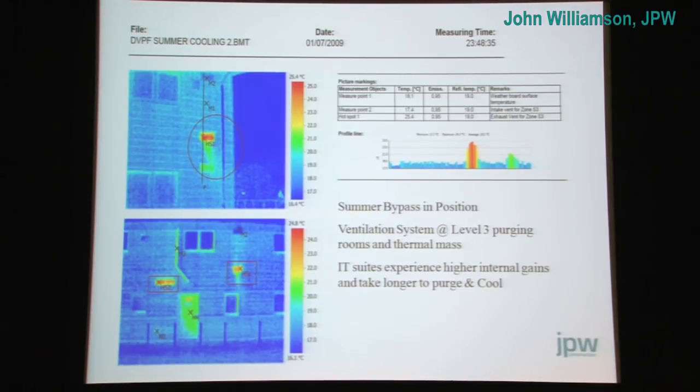We are heading for that double whammy. We've had the hottest summers and the coldest winters on record the last 2 years in a run. High air conditioning loads, high heating loads. And luckily, here we are, pulling in 18 degrees, in at midnight, 26 degrees coming out of the building, out of the ventilation units. By the next morning, we've dragged it down to 16. So we're pleased that we've managed to keep the comfort levels. 4 seasons in one day, the crossover seasons, can be a bit tricky. We are trying to rationalise that.